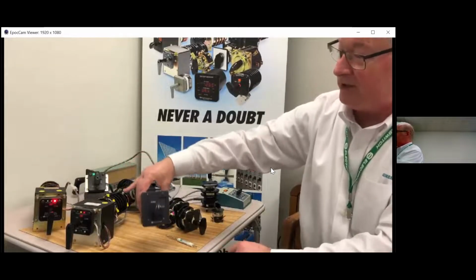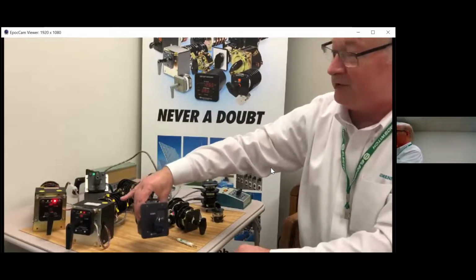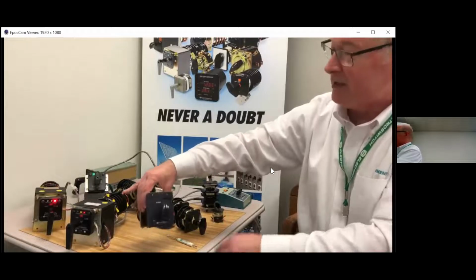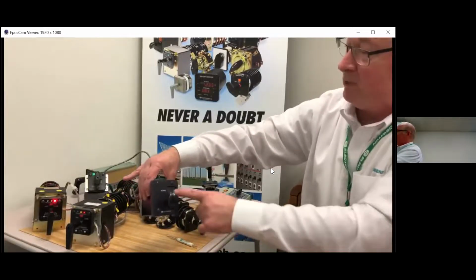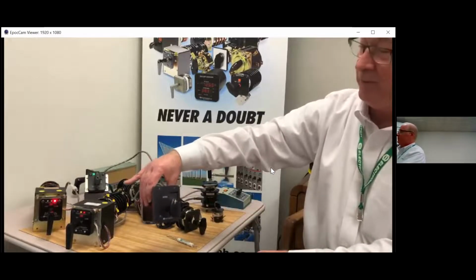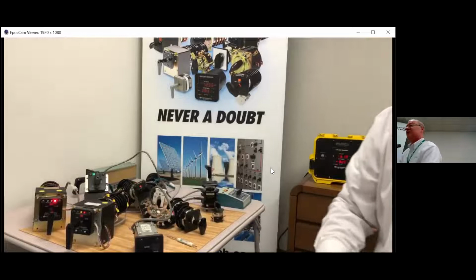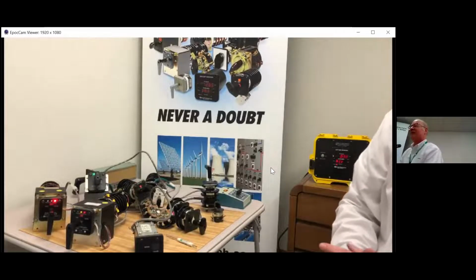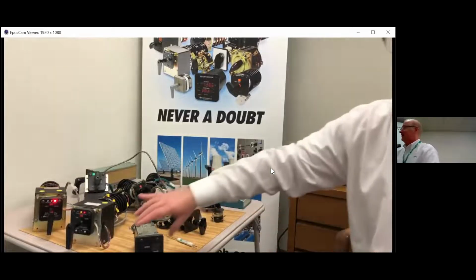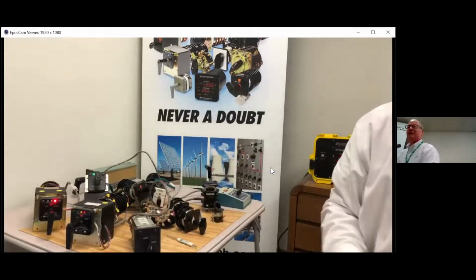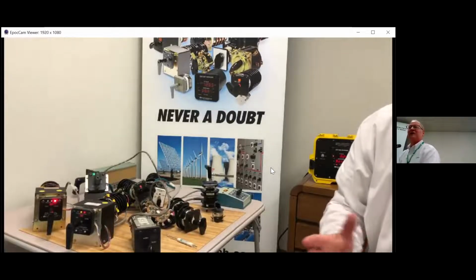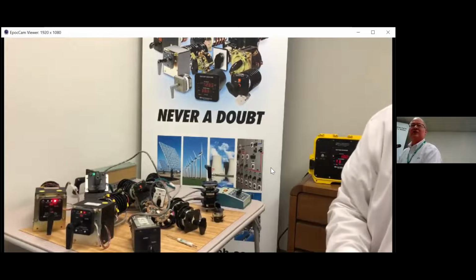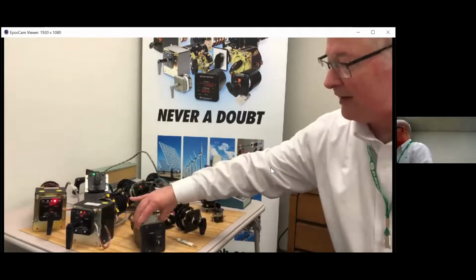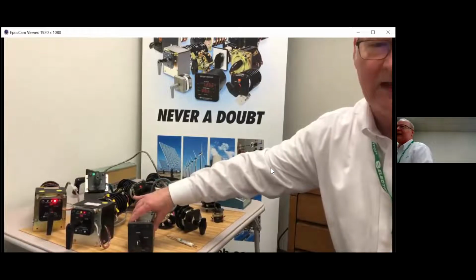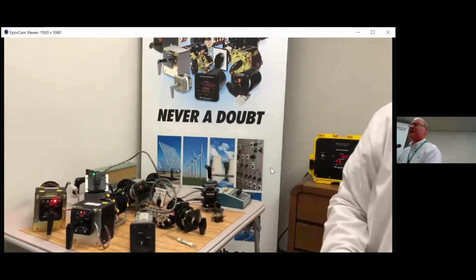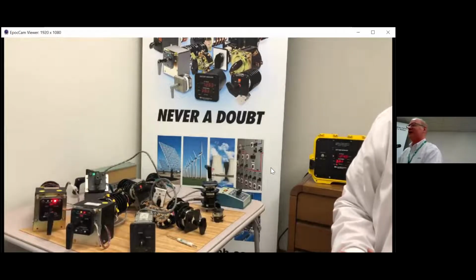But a nice function that this latching device allows you to do is, again, with maintenance purposes, this happens to be a tagging relay, and it's marked at normal and tagged on the switch. And for those maintenance outages that you need to have where you bring contractors in who have to tag their locks on the particular devices that they're working on for safety purposes. At the supervisory level, you might want to have a tagging relay that adds the final supervisory lockout tag for that particular breaker.